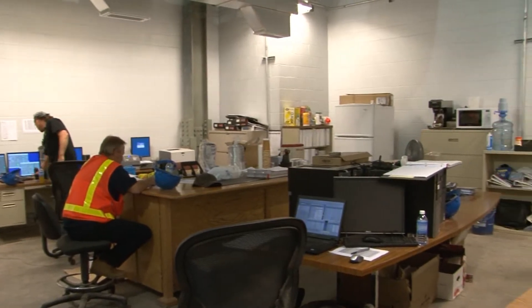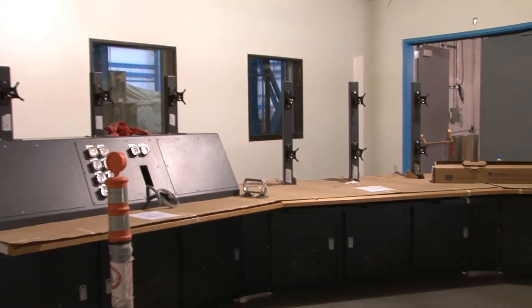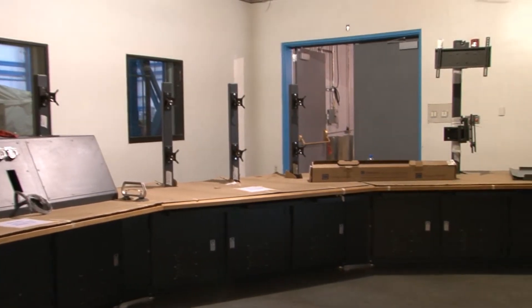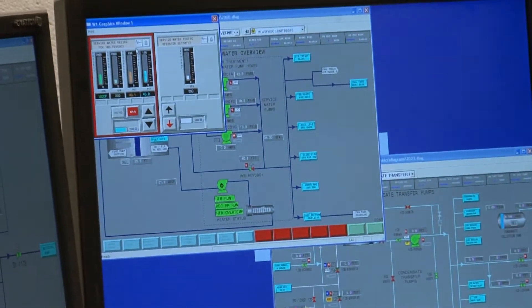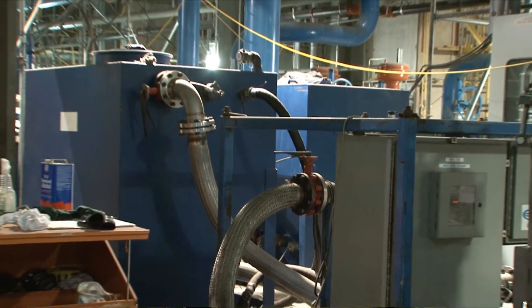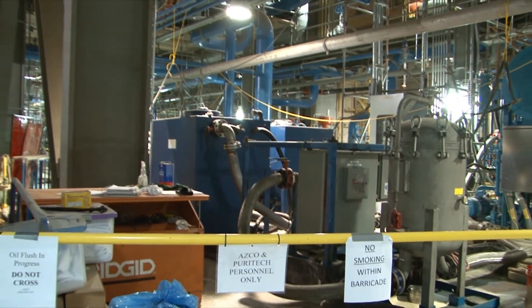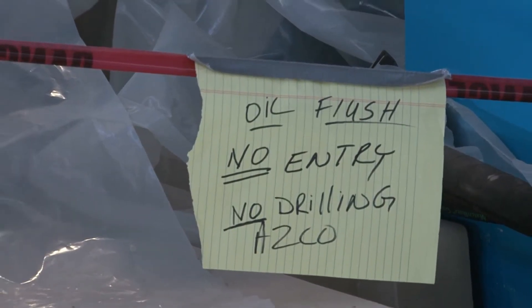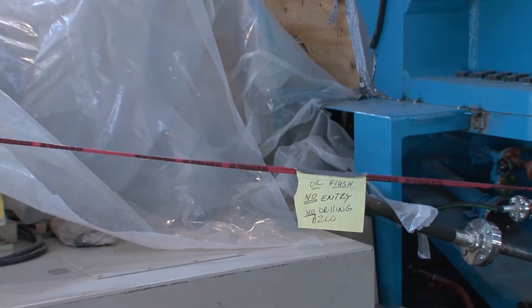The pumps and motors under Basin Electric's control are monitored from a temporary control room. The permanent control room is still under construction. Today, control room operators are watching the turbine lube oil flush. We're pumping oil at about 2,000 gallons per minute through the entire lube oil system to flush it and any impurities that might be in there. Oil will flush through the system for about a month.